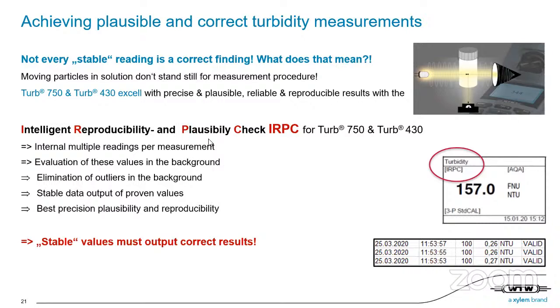But also with this IRPC, so intelligent reproducible, that if you place it again and again, you get the same value, as well as that the values are plausible, that they are good. This is checked during measurement. So we internally measure some readings, we evaluate these values in the background, we eliminate outliers, which means if there is a complete, either by accident, too fast moving, or too turning, or just one big particle in a whole bunch of small ones. So all these scattering effects, which are just giving peaks which are not in the average, are eliminated, and then we make the output of data which is not oscillating and showing this dancing and dangling.